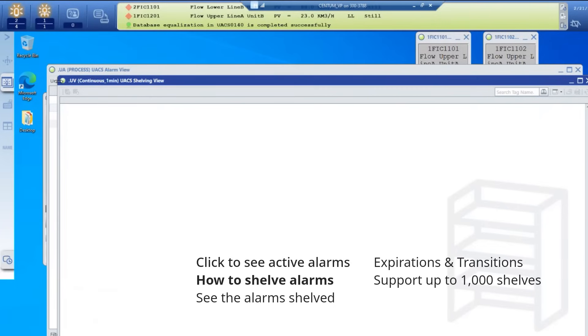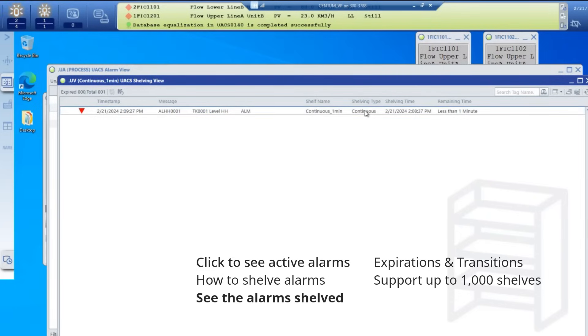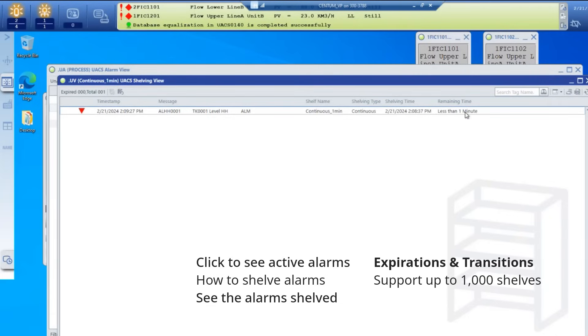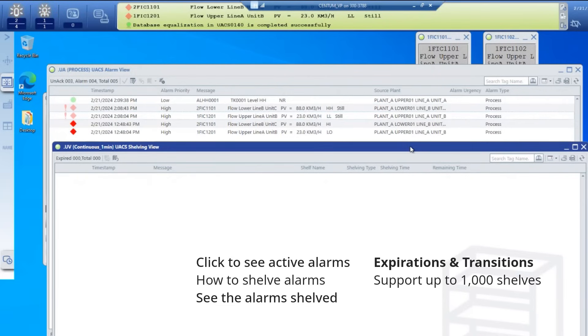If I click on it, I can see that this nuisance and chattering alarm is now shelved. In the shelf, I can see it's still recovering between normal and alarm. I can see the name of the shelf, the type, and the shelving time. I can also see the remaining time is less than one minute for this demo. After the one minute expires, the shelf has now transitioned back to the main alarm view.